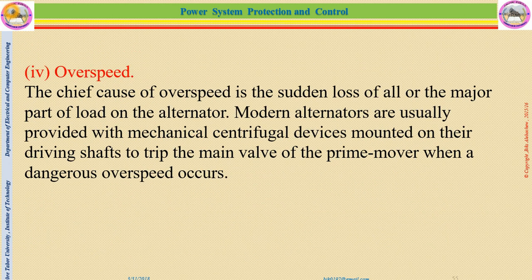The other fault, the fourth one, is overspeed. The chief cause of overspeed is the sudden loss of all or major parts of the load on the alternator. For example, in a typical case, if Bardar substation fails, at that time there is a great problem for our electrical system. So in that sudden loss of Bardar substation, overspeed may happen on generation stations and the like.